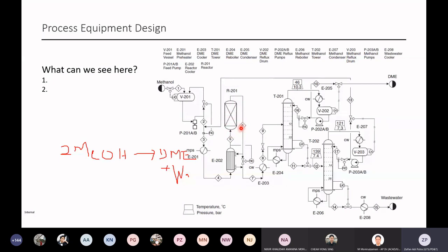For example, say this pressure drop is like half a bar, just to get a typical number, and this one is half a bar. And then for the line, you can allow about half a bar pressure drop. So you have half a bar for the line, another half a bar for this flow meter, which means one bar. Half a bar here makes 1.5, half a bar there makes 2 bar. And this is 15 bar. So the discharge pressure here should be 15 plus 2 bars, which is 17 bar, right?